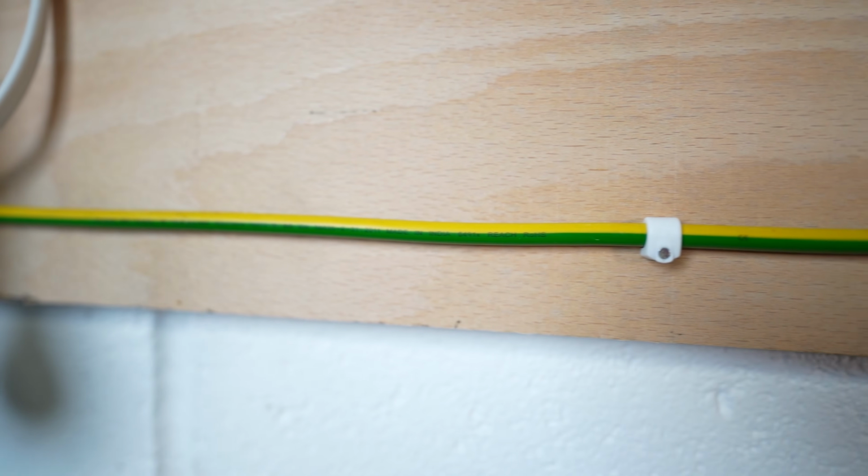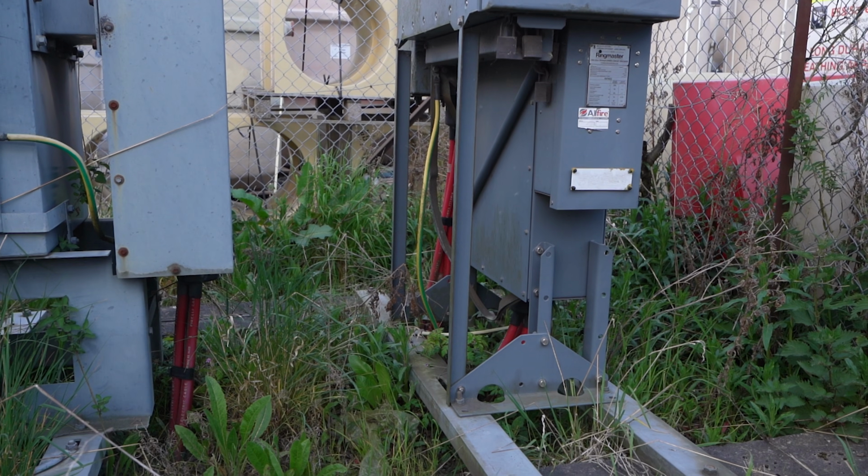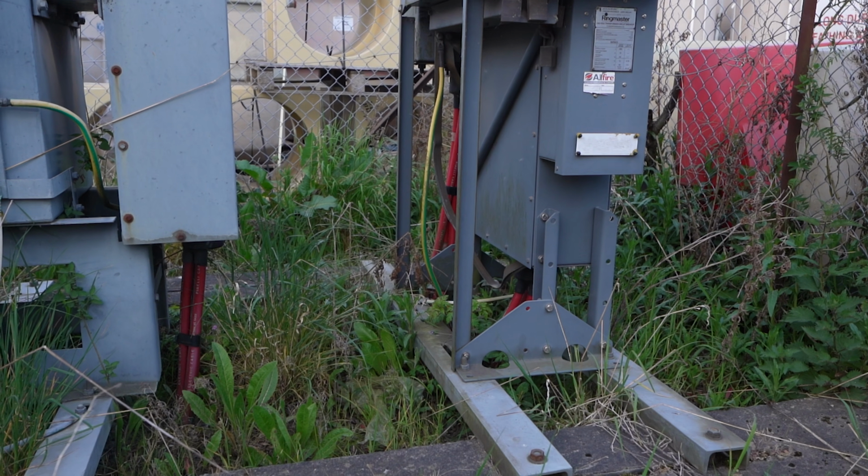However, in the commercial industrial world, bonds can be hundreds of meters long. They can be across vast areas. So just don't be afraid to walk into a switch room and see a 35, 70, 95, 120 mil bond, big, thick earthing conductors. It's just going a further distance. It's been designed accordingly to either meet that value or obviously in accordance with the supply conductors. But just don't be freaked out when you see those bigger bonding conductors, because it's just on a vaster scale.